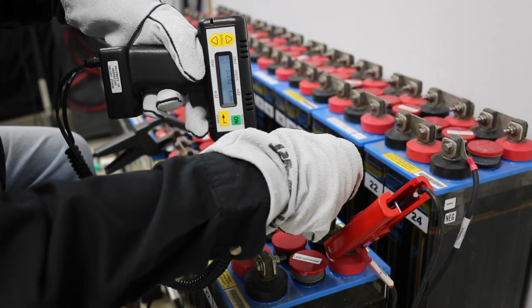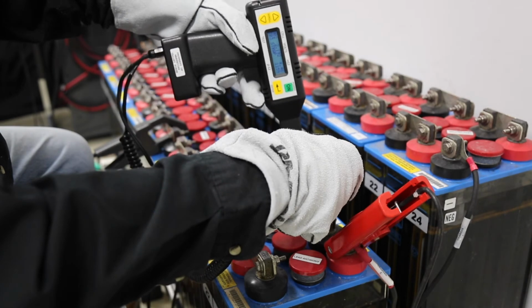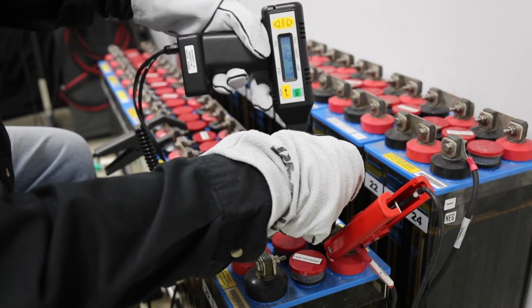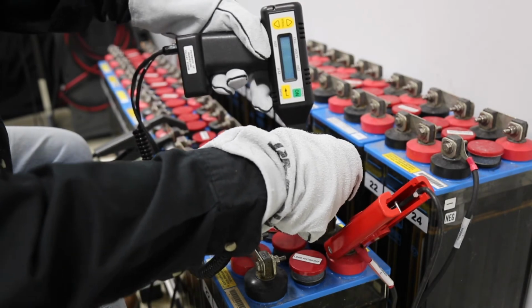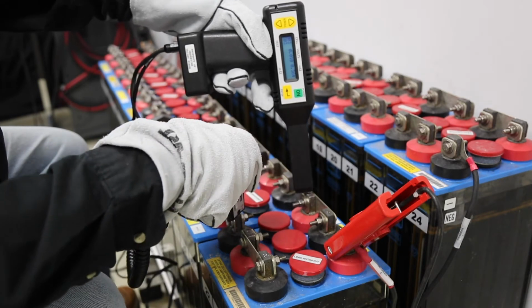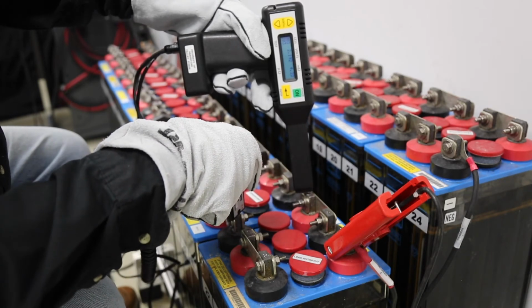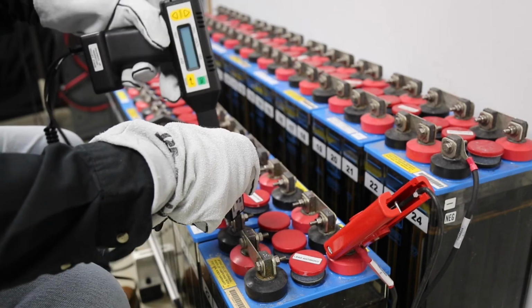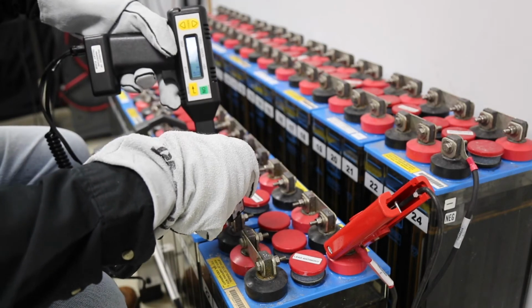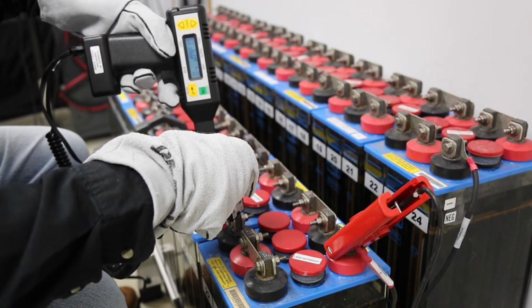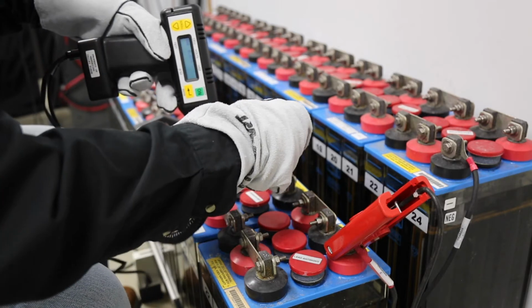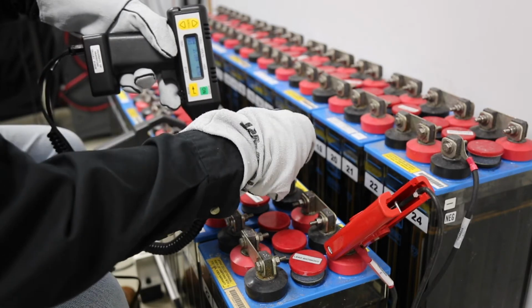You only move one probe at a time. This makes it far less likely of making a mistake, especially when you're testing long strings. The more probes you have to move, the more likely it is to make a mistake. Now, for the purpose of this demonstration, I'm just going to measure 4 cells. Now, when testing a string, there's always one less strap than cell.